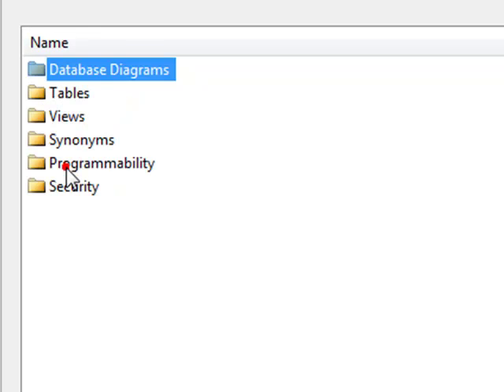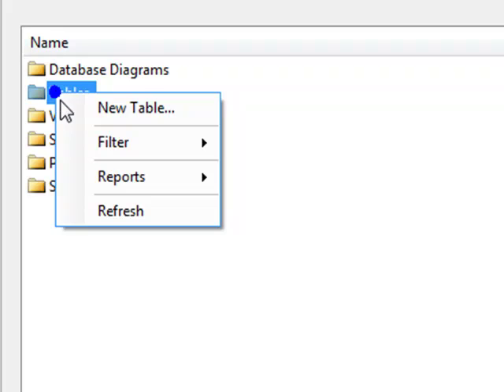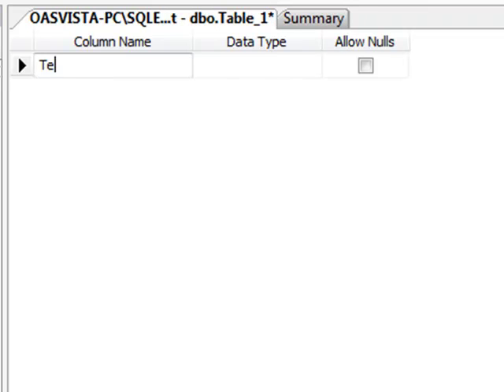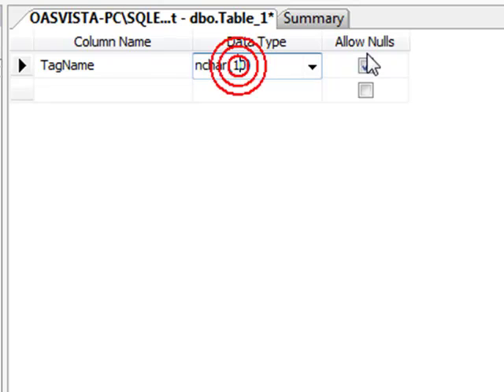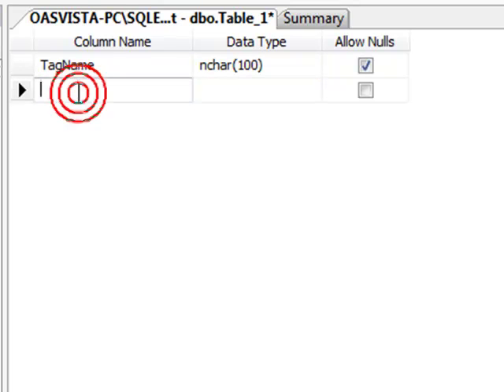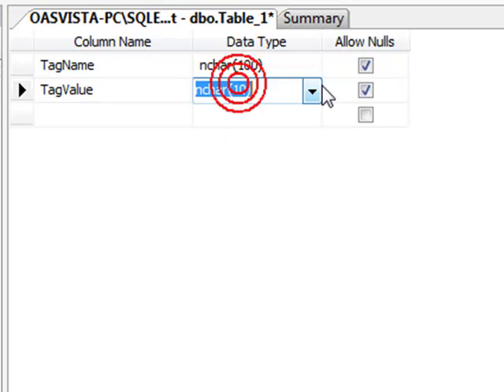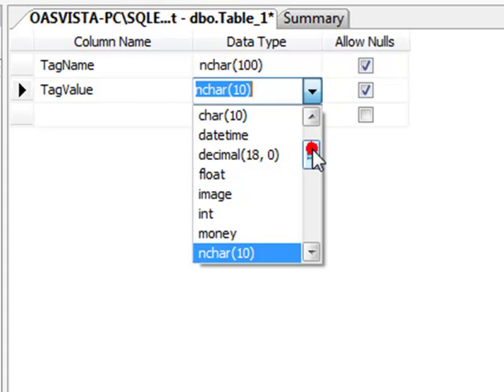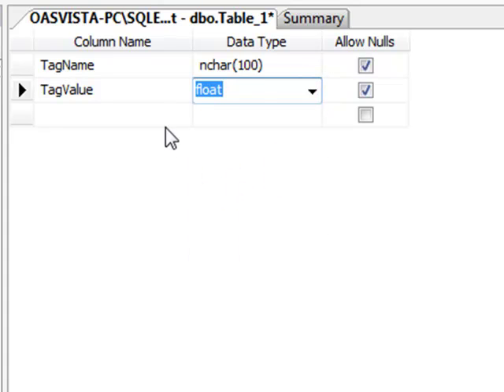Double-click on the RecipeTest database. Select the Tables object, and right-click on it to add a new table. Now we need to define the field names that will contain the tag names and the values that we want to receive from the database. The first field I'm going to define, I'm going to use the name tag name. Under the data type, I can use a character type with a length of 100. The second field is where the values are going to come from. For this field name, I'll use the name tag value. And we can set the data type to an integer, Boolean. Here, I'm going to use the type float.